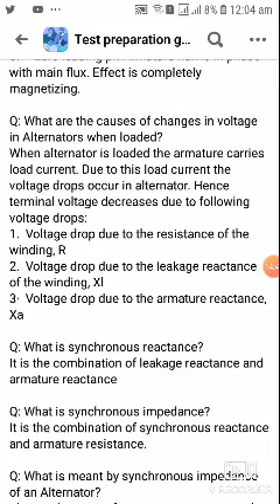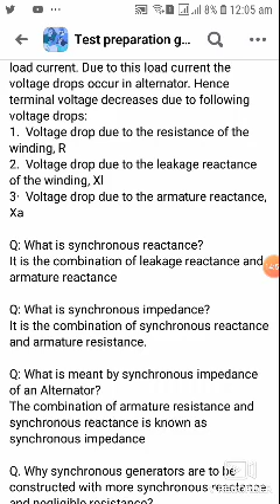When an alternator is loaded, the armature carries load current. Due to this load current, voltage drops occur in the alternator. Hence, terminal voltage decreases due to the following voltage drops: voltage drop due to the resistance of the winding, Ra; voltage drop due to the leakage reactance of the winding, Xl; and number 3, voltage drop due to the armature reactance, Xa.